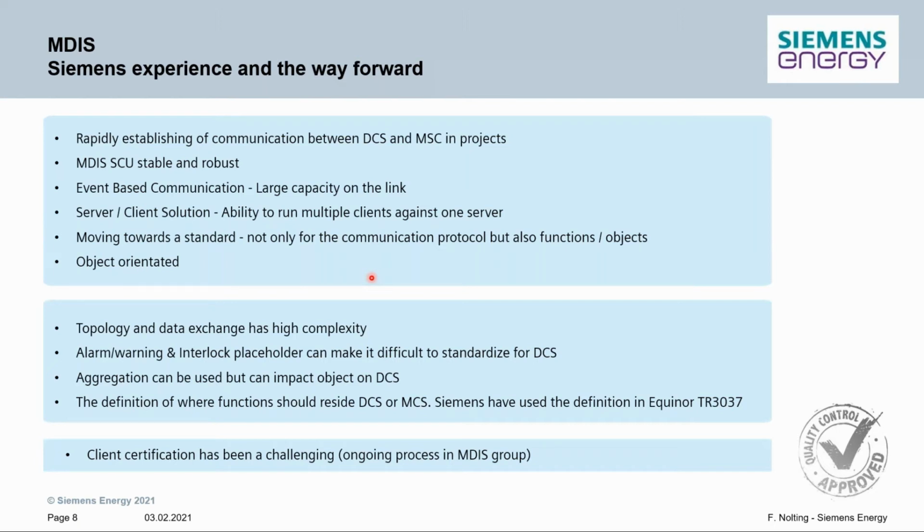On the other hand, we have also seen that the topology and the data exchange and so on is getting more complex, and then we need to make sure that our engineers have more competence about the MDIS. We have seen that MDIS includes certain freedom, for example, that it's possible to define alarms and warnings, interlock placeholders on individual objects, and that can be difficult, as I showed you before, to standardize. So that's something that we are working on also in MDIS. As Paul mentioned, we are trying to standardize some of the alarms and warnings so that it's easy to implement.